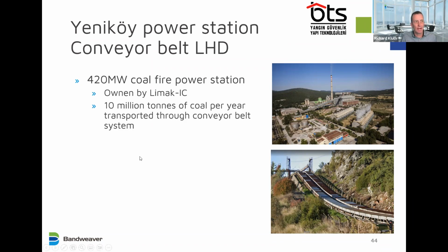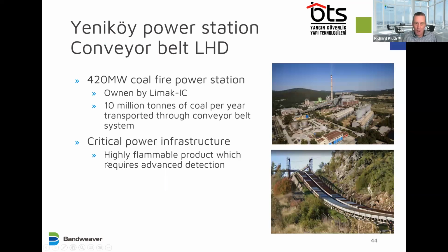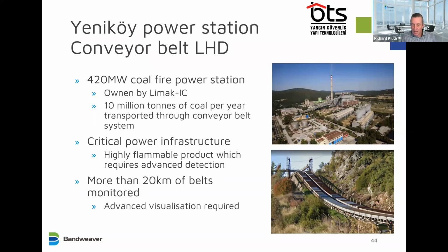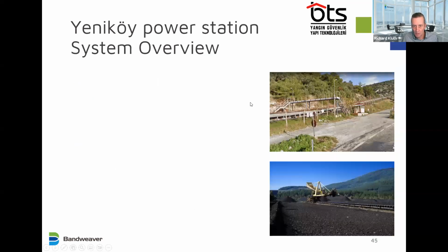And they've had a number of issues over the years with the bearings in the rollers seizing up, heating up, and causing fires. It's really critical power infrastructure, highly flammable product, which requires advanced detection. And so they're really looking for something that can detect fires early and prevent any disruption and damage to the conveyor belt. In this case, there's more than 20 kilometers of conveyor belts monitored, and because there's a lot of different sections, they really wanted advanced visualization. So we'll show with the MaxView software how that was carried out.